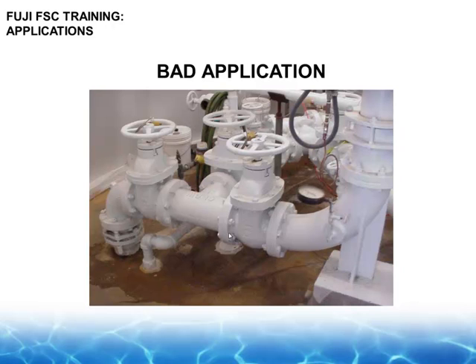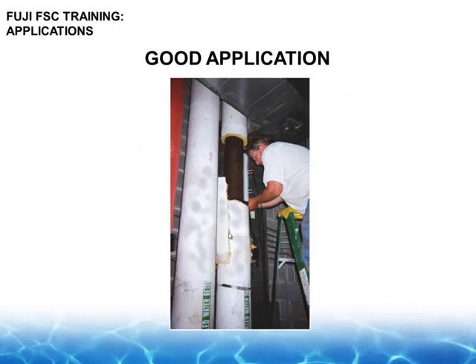This is a bad application. And the only thing you can do is go upstream or downstream. You can't make the flow meter work on something like this, so you don't try. So an upstream, downstream may actually require somebody getting a backhoe out and digging up a pipe. So if that much labor is required before you do a flow study, you need to do that in advance and have somebody do the work before you get to the job site to save yourself a lot of time.